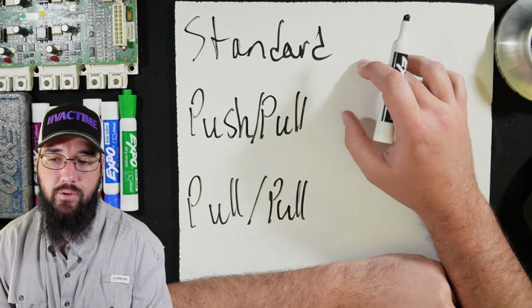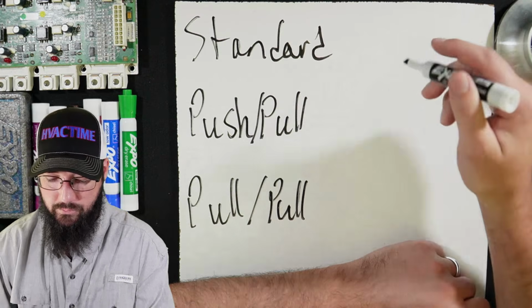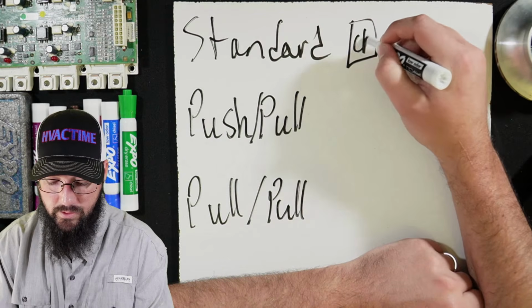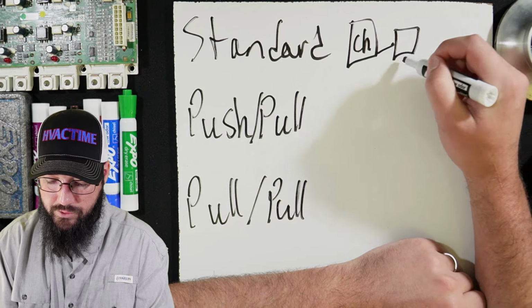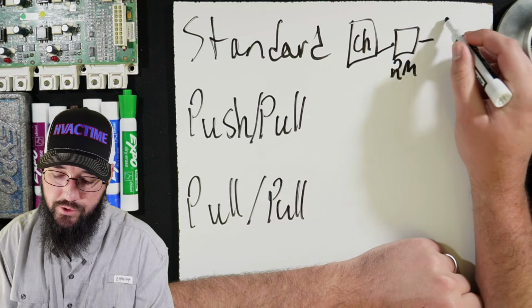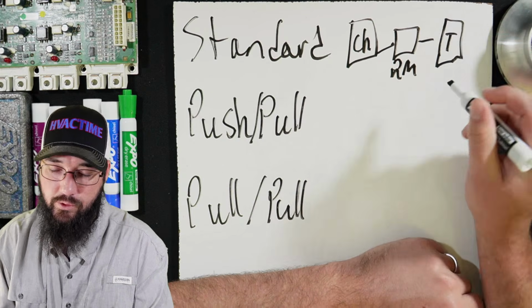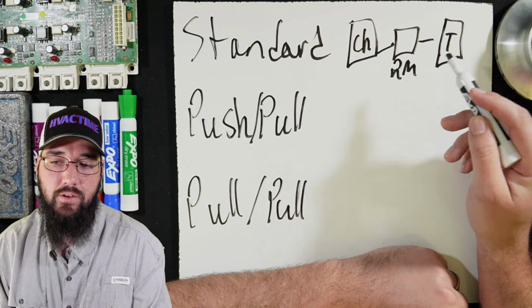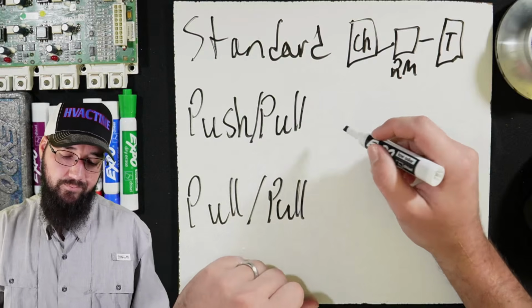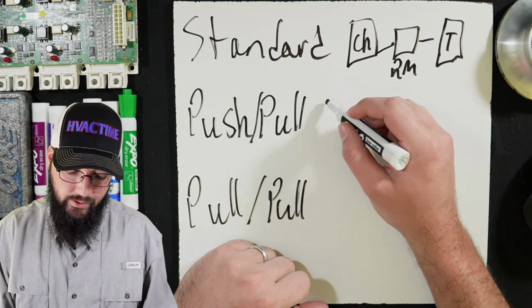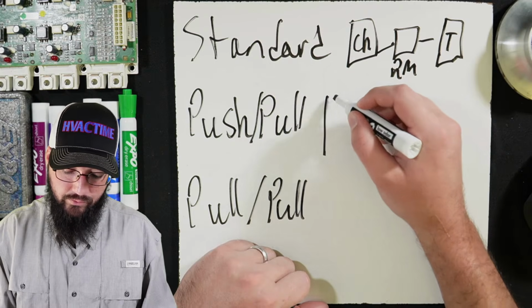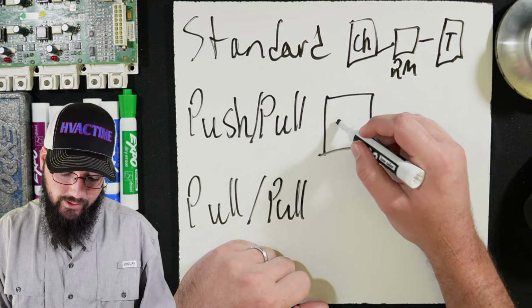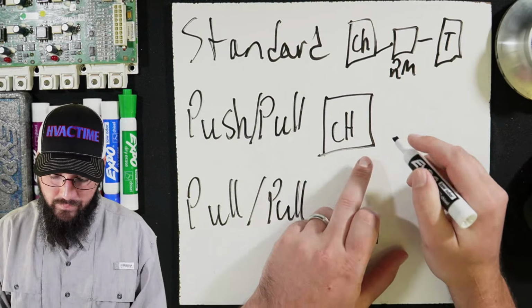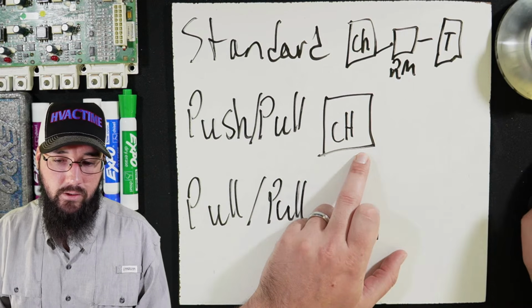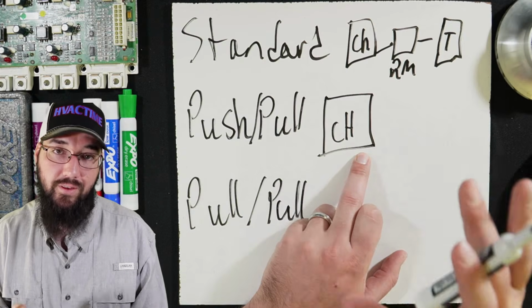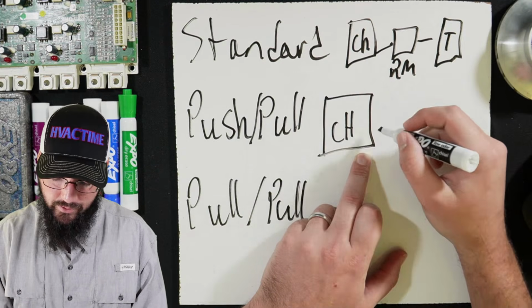All right, so standard recovery is exactly what you would think it would be. We have our chiller, we come out of the chiller into the recovery machine, out of the recovery machine into our recovery cylinder. I'm just going to refer to it as tank, okay? Basic process. Push-pull, we're referencing a slightly more advanced version. I say slightly, I mean this is a more advanced practice in general. It's important that we have access to the liquid in the machine, which is where the evaporator becomes really important. We'll get into that in just a minute.